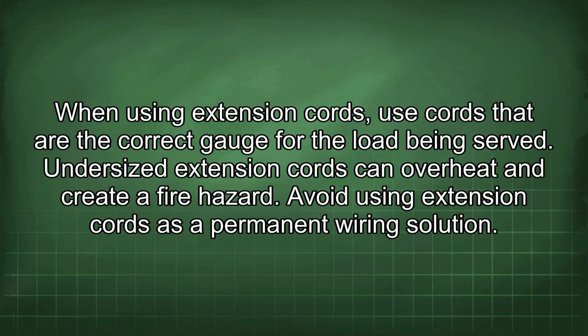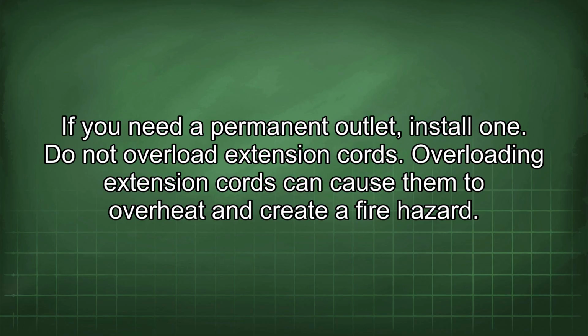When using extension cords, use cords that are the correct gauge for the load being served. Undersized extension cords can overheat and create a fire hazard. Avoid using extension cords as a permanent wiring solution. If you need a permanent outlet, install one.